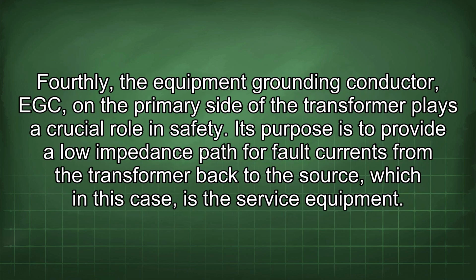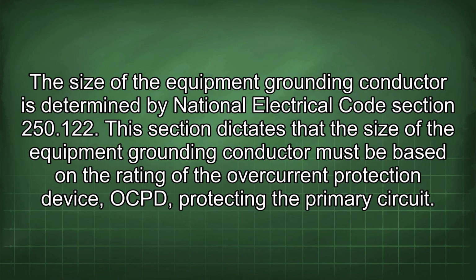Fourthly, the equipment grounding conductor, EGC, on the primary side of the transformer plays a crucial role in safety. Its purpose is to provide a low impedance path for fault currents from the transformer back to the source, which in this case is the service equipment. The size of the equipment grounding conductor is determined by National Electrical Code Section 250.122. This section dictates that the size of the equipment grounding conductor must be based on the rating of the overcurrent protection device, OCPD, protecting the primary circuit.